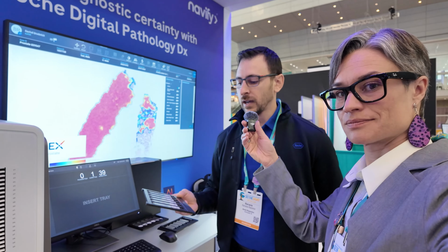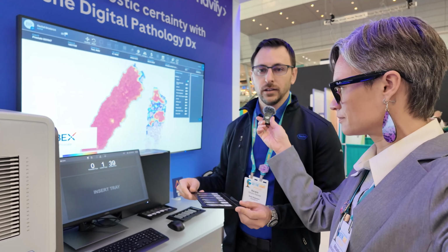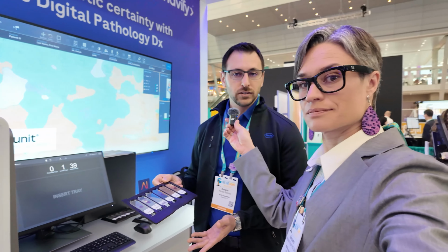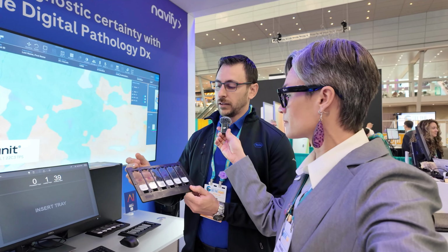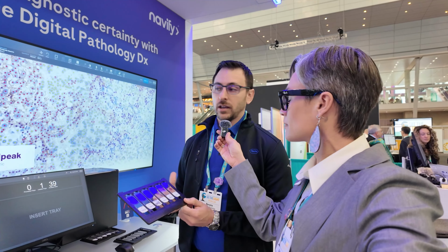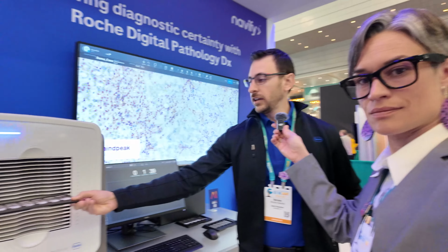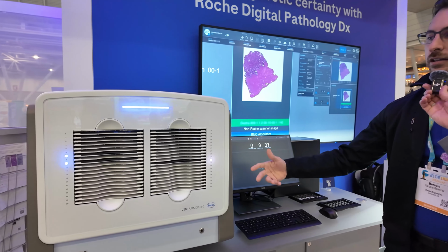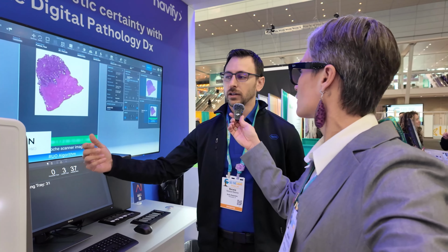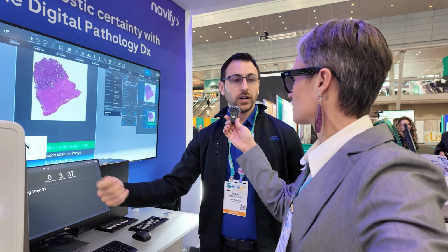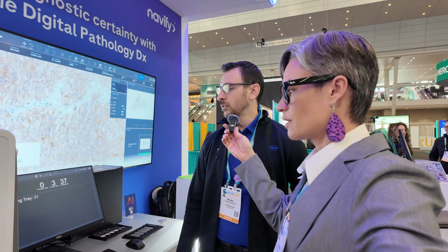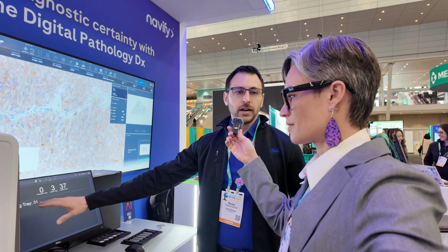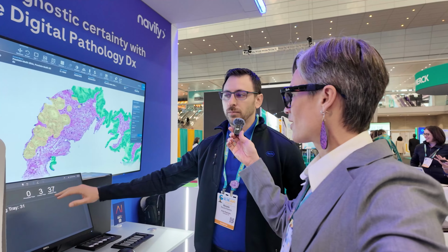So unlike most of the other scanners in the market, what it does is basically take trays. So it doesn't pick individual slides. It actually picks these trays with 6 slides each, and you slide the tray in. And then it's basically continuous workflow. So you can take out trays and load trays at any given time. Right now it's taking in the trays, actually a working demo. It's going to do a thumbnailing, and then it will let you approve or...